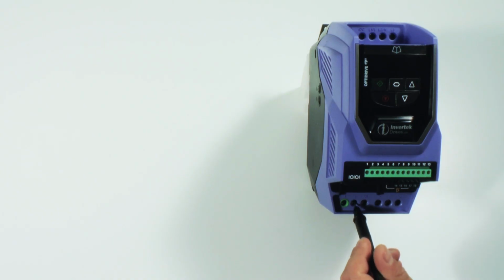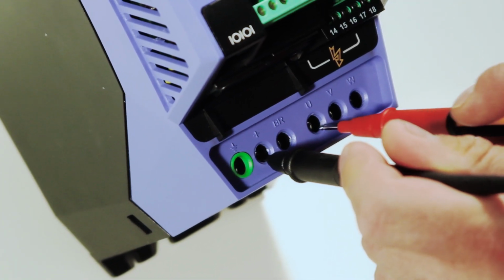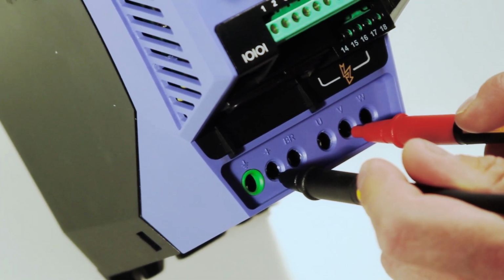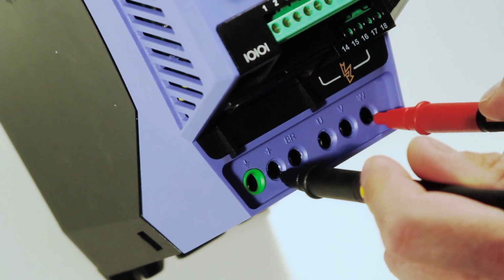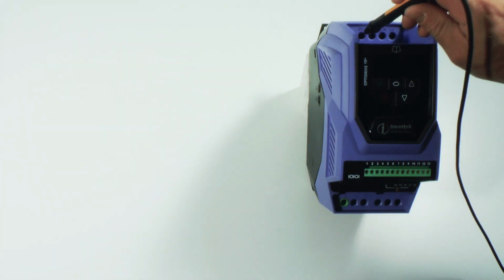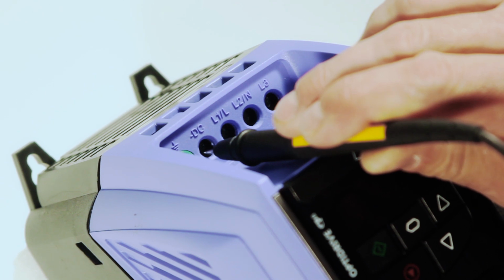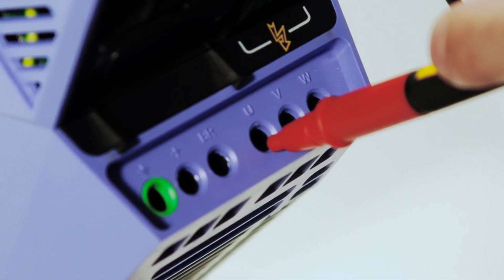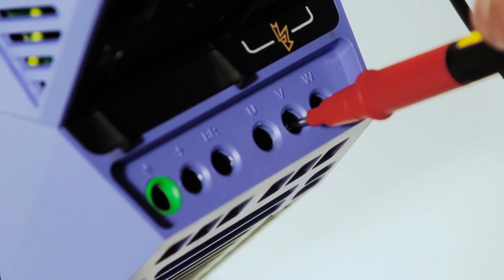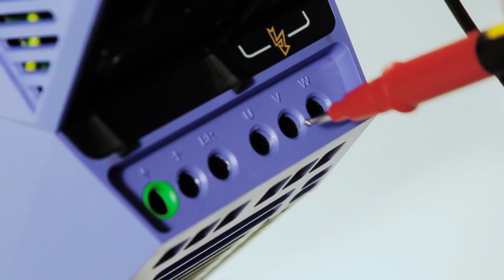Output circuit check. Place the black lead on the plus DC bus point and measure with a red lead to the U phase, V phase and then the W phase. Place the black lead on the minus DC bus point and measure with a red lead to the U phase, V phase and then finally the W phase.